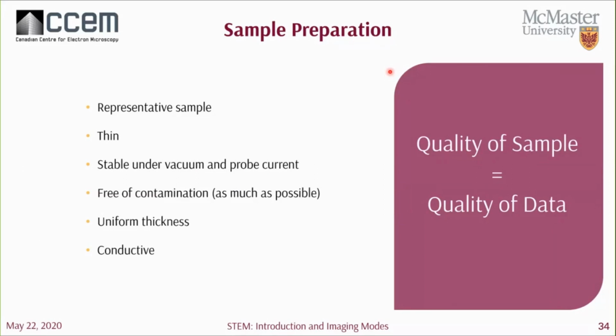And since we're collecting transmitted electrons, you'll need to make sure that you have a nice thin sample. Generally, the thinner the better. If you have a thick sample, you won't be able to get good signal from it. You also have to think about whether your sample is stable under the vacuum or the probe. Is it free of contamination? This is kind of hard to do, but you can do some plasma cleaning or use really pure solvents to reduce contamination as much as possible.